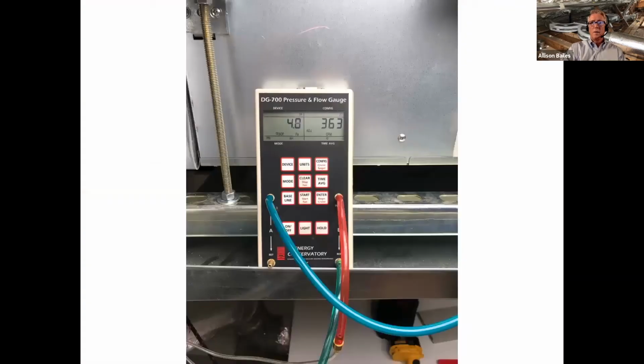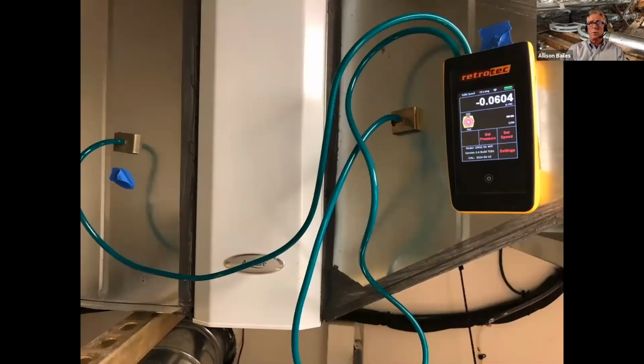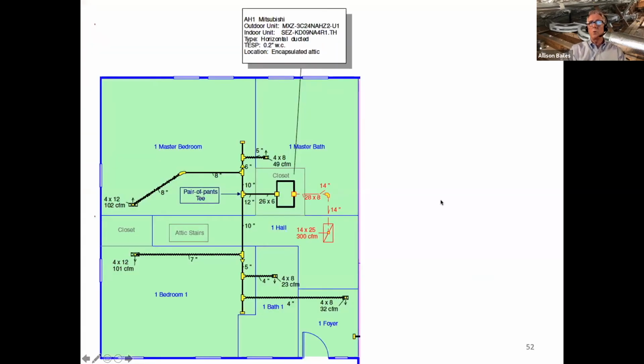But that 0.09 inch of water column static pressure was with this airflow. So 363 CFM, cubic feet per minute of air, total airflow, which is about what it's rated for. So we were getting full airflow. This was the pressure drop across the filter, 0.06, so really good. We'll talk about filters some more. I've got another myth coming up, and we'll talk about filters there.